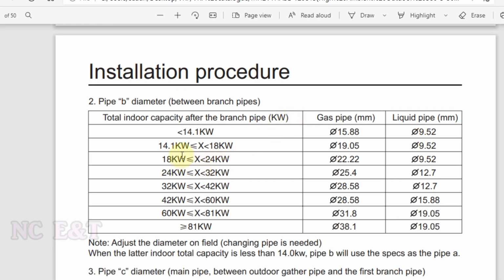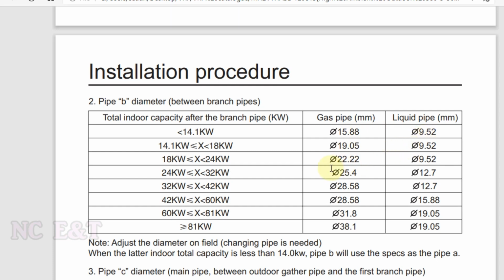Like this. If this capacity is less than 14 kilowatt, then the gas pipe will be 15.88 mm and the liquid pipe will be 9.52. In the same way, we can select the pipe diameter for the whole pipe length from the table that is provided by the manufacturer of the VRF units.